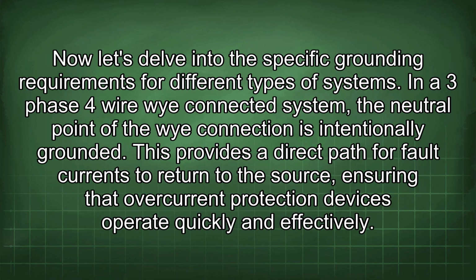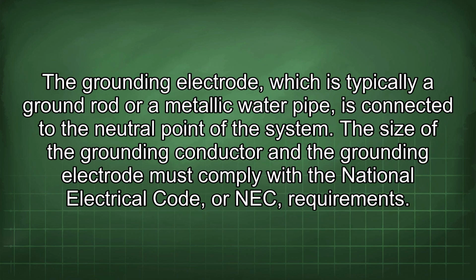Now let's delve into the specific grounding requirements for different types of systems. In a 3-phase 4-wire Y-connected system, the neutral point of the Y connection is intentionally grounded. This provides a direct path for fault currents to return to the source, ensuring that overcurrent protection devices operate quickly and effectively. The grounding electrode, which is typically a ground rod or a metallic water pipe, is connected to the neutral point of the system.